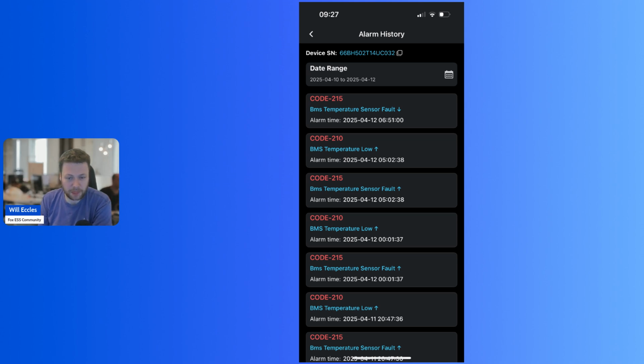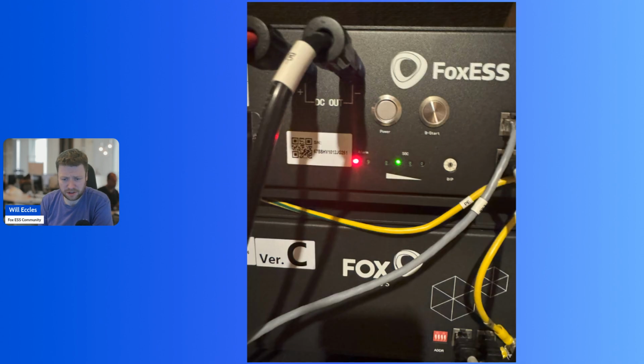Clearly there is something going on with this BMS and the temperature sensor, I thought. So I attended site, got the error message. Let me just bring up the picture of what it looks like on the BMS, because that's a pretty good indicator. This is what the BMS looks like - talking about the HV 2600s now, depending on the battery model there may be a slightly different sequence of lights, but on the older battery sequence you can see a left red alarm light and the second state of charge light was flashing.